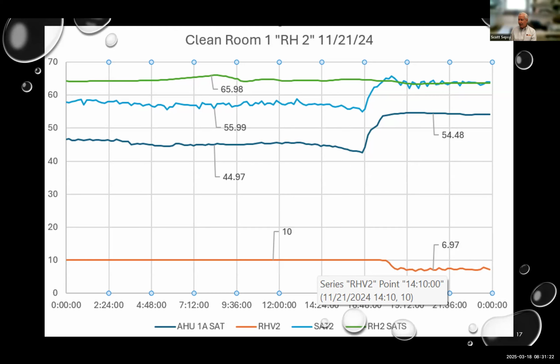When labs need deep dehumidification, as this slide shows, which may be in a summer or shoulder season, and internal loads are light, the reheat coils will see their toughest duty. Hot water preheat coils or boosted glycol preheat coils should also be studied and tested. Capacity analysis could also be done looking at product data and submittals to cross-check.